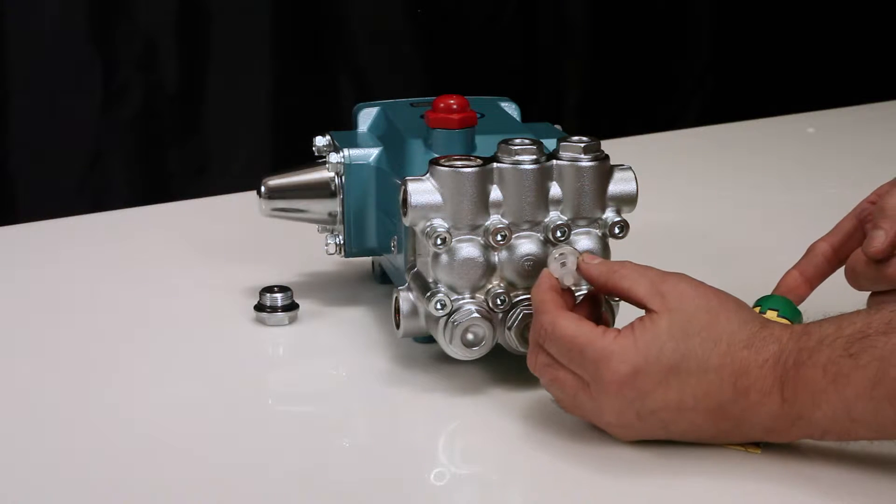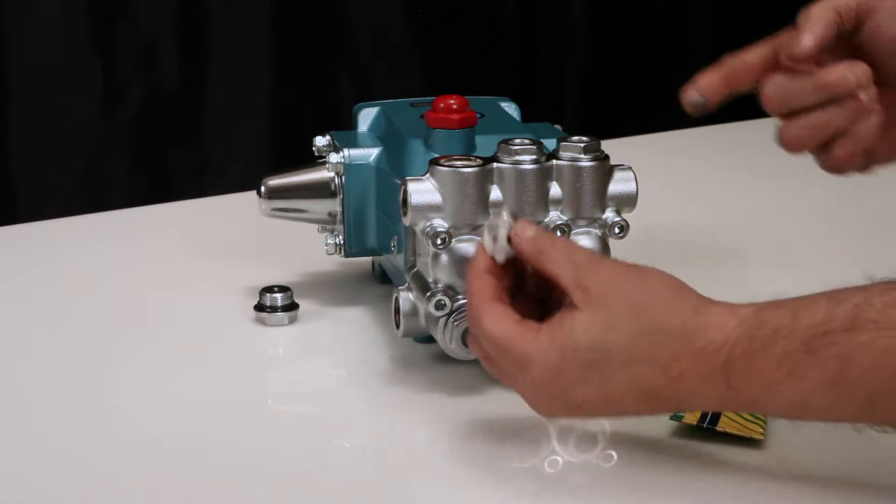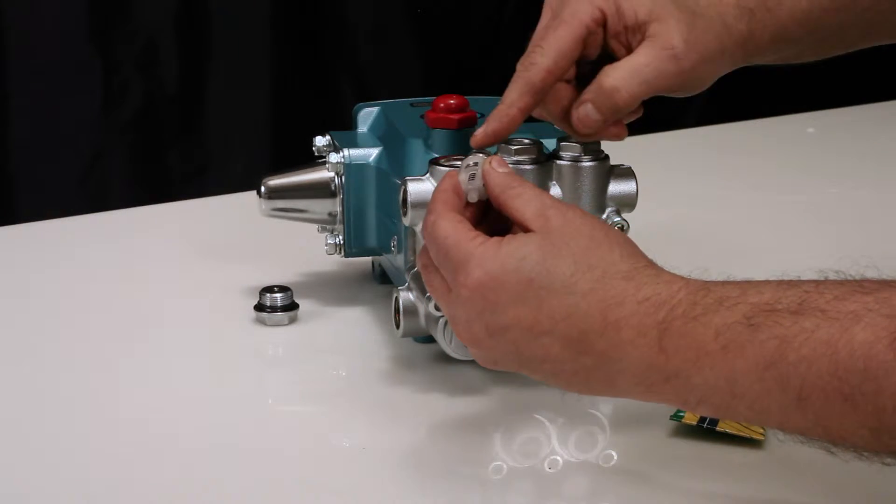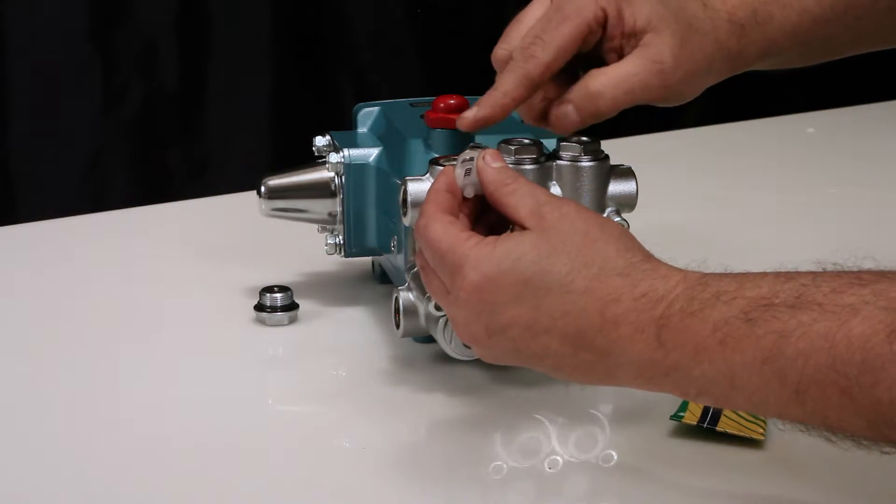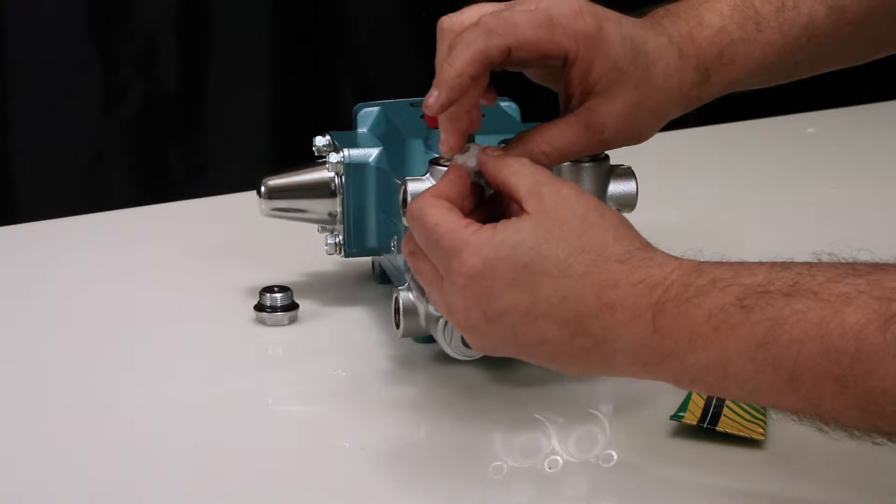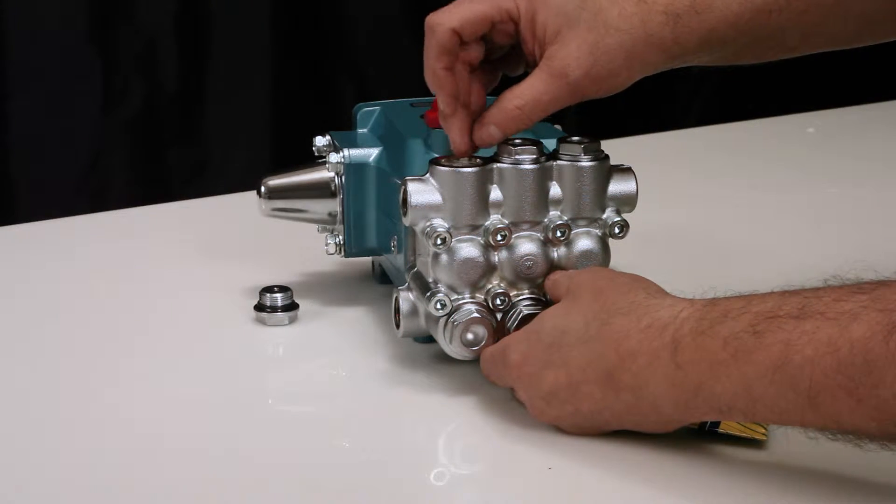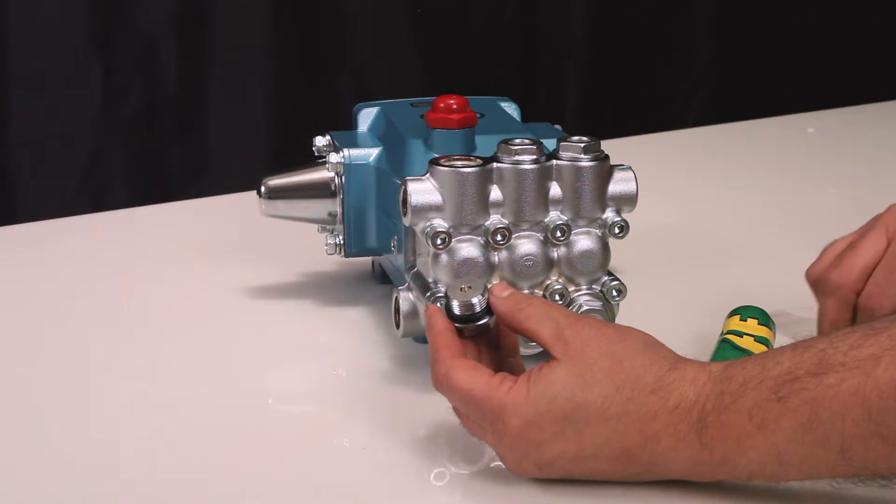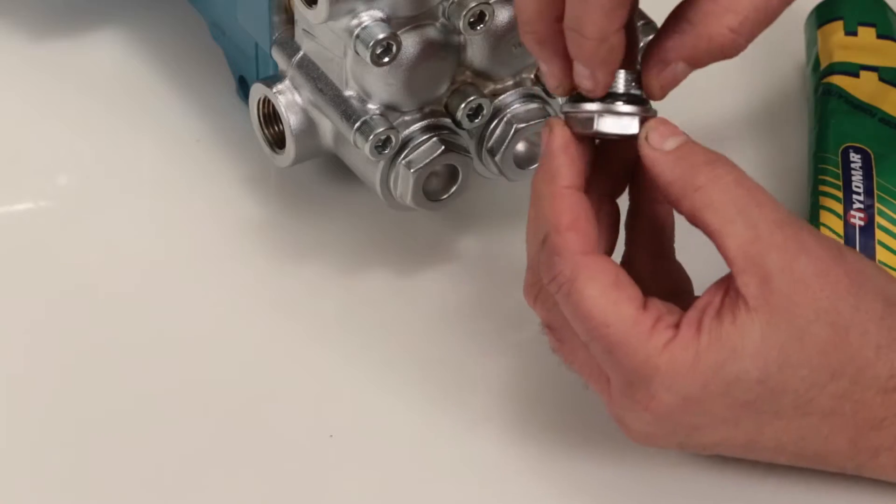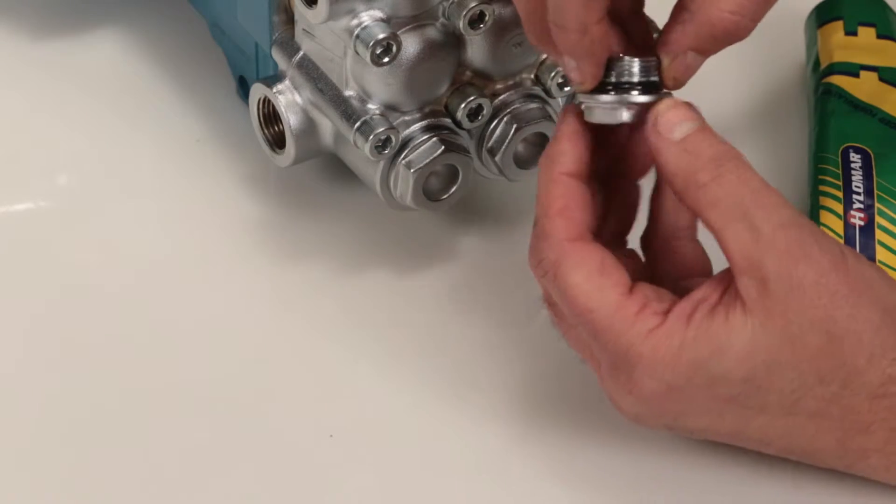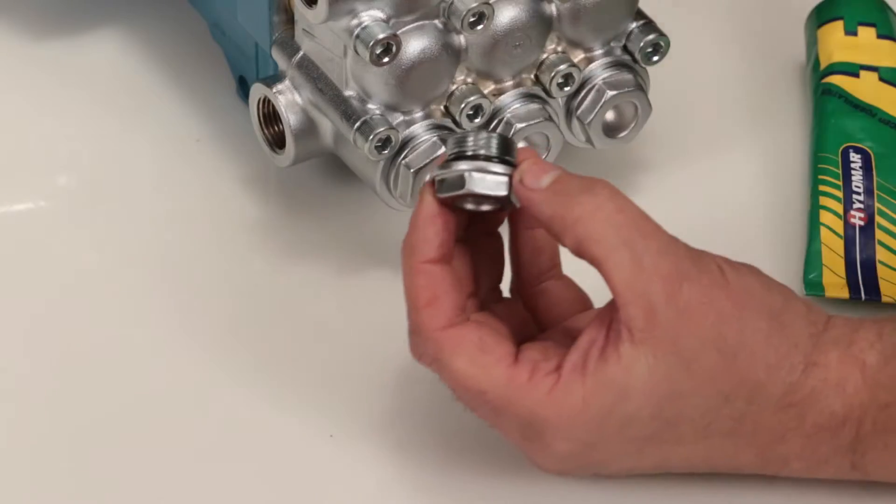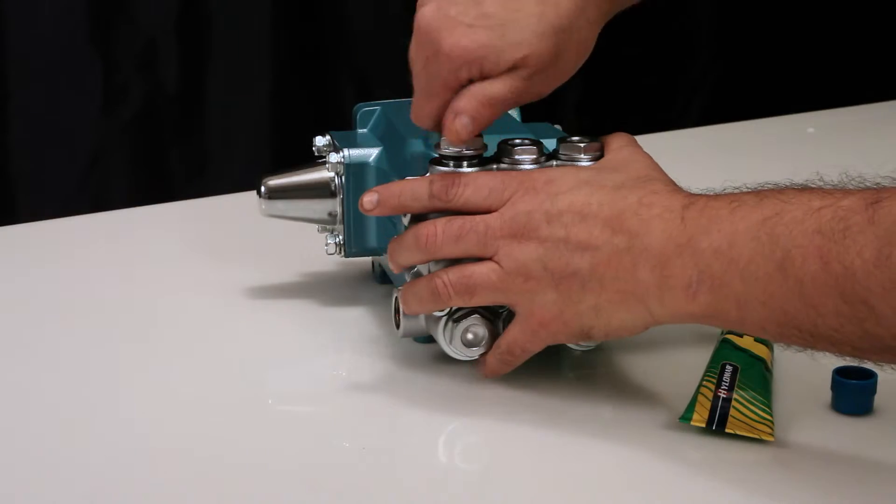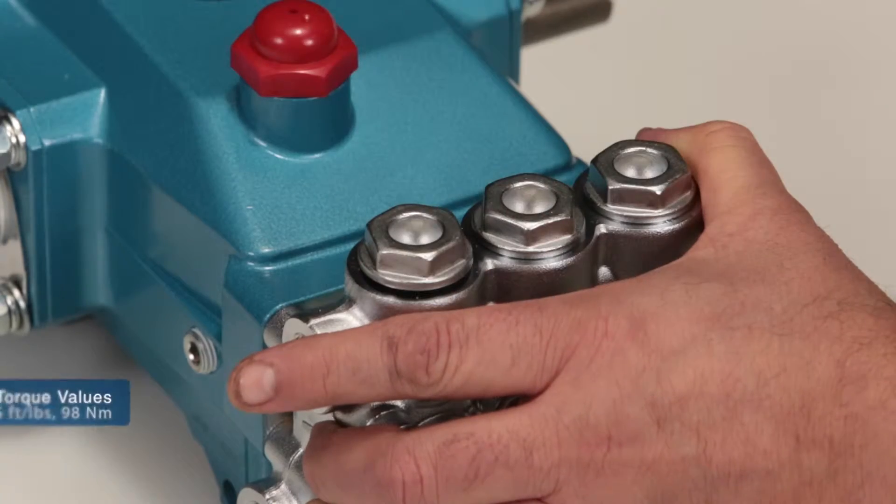Before installing the new valve assembly, lubricate the O-ring and backup ring on valve seat with liquid gasket. Next, insert valve assembly into manifold and press into place. Lubricate the O-ring and reinstall the valve plug. Torque to specification.